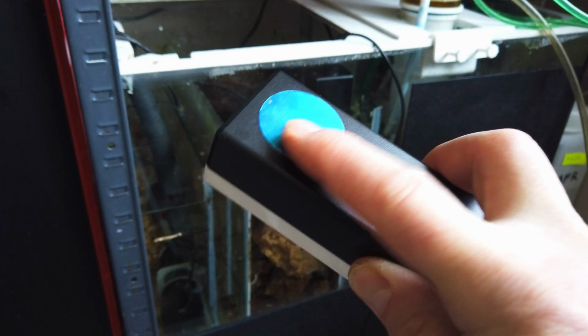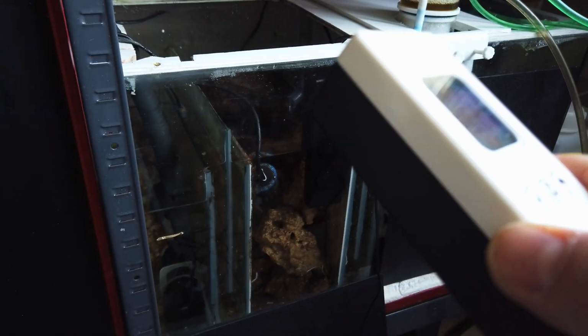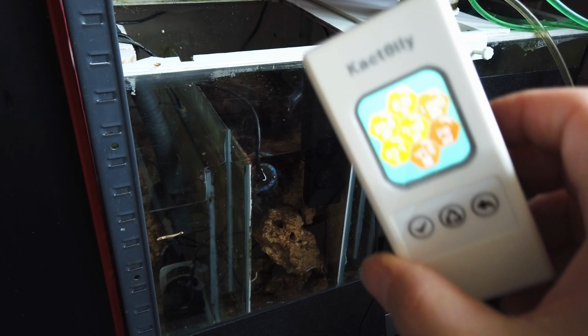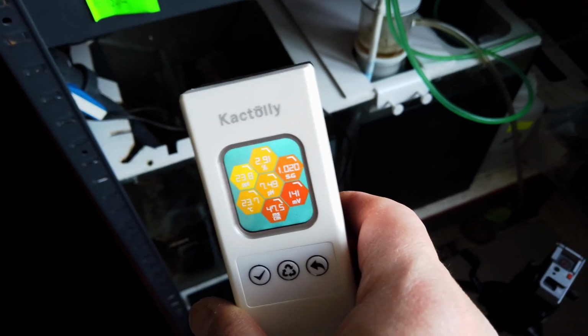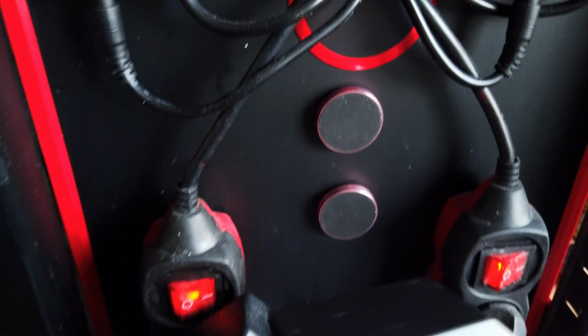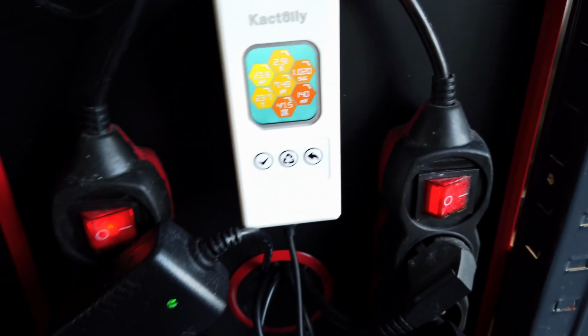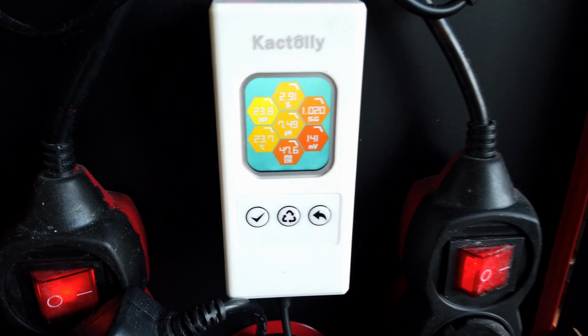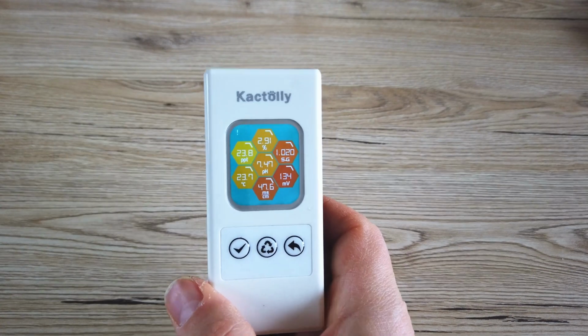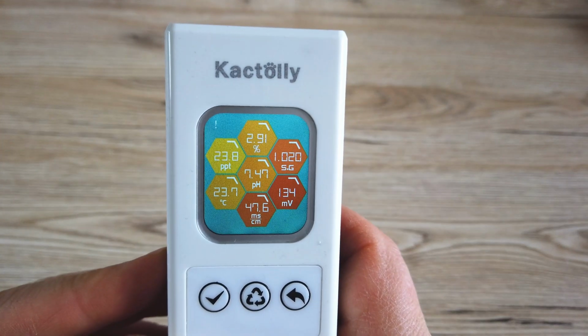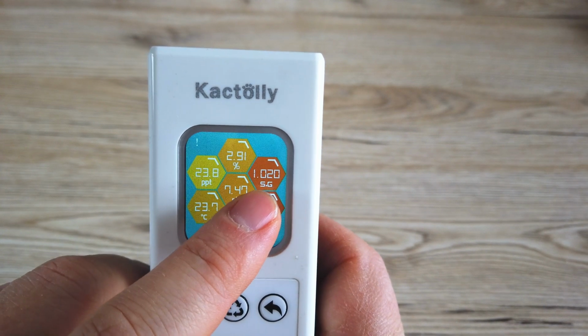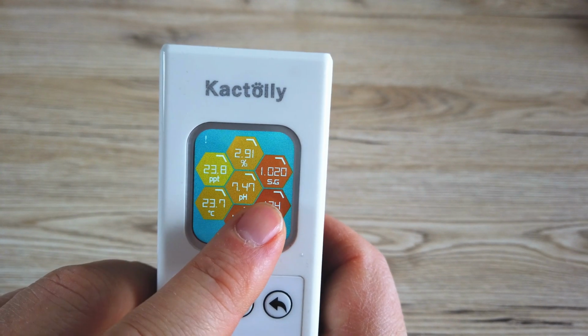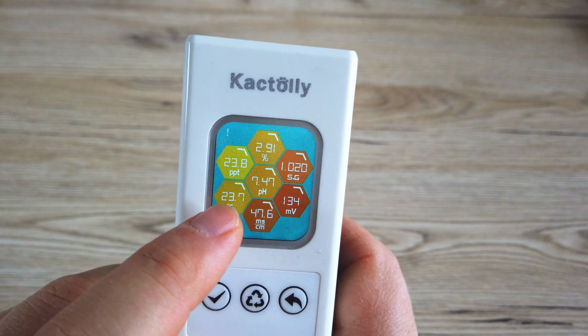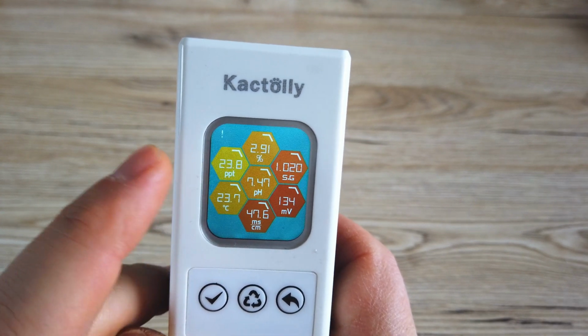Here I glued metal plates that attach to the magnets on the control panel, which I glued there. You can see it here. This is how easy it is to attach the display to the panel. This is the advantage of the wireless connection to the probe. Okay, let's look at the values. But as I can see, specific gravity is incorrect, and also the pH seems to be low. And let's also check the temperature.